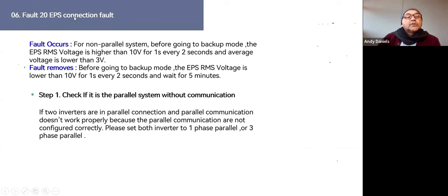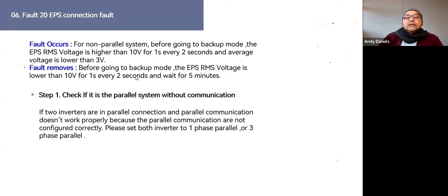Fault 20 is an EPS connection fault occurring in a non-parallel system. Before going to backup mode, the fault triggers if the EPS RMS voltage is higher than 10 volts for one second every two seconds and the average voltage is lower than 3 volts. If two inverters are in parallel but the parallel communication is not configured correctly, make sure both inverters are set to the same phase — single-phase parallel or three-phase parallel.